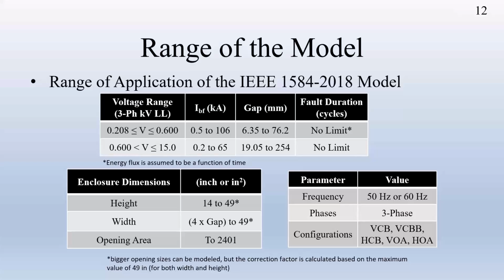So when I run the test, I will basically follow the UL standard, and for the high voltage, we use the BIL as a reference. In the 2002 model, it doesn't consider the enclosure size, and for the 2018, we do consider enclosure size. Here we put it at 49, and actually you basically run into the 49 and 50. They are about the same.